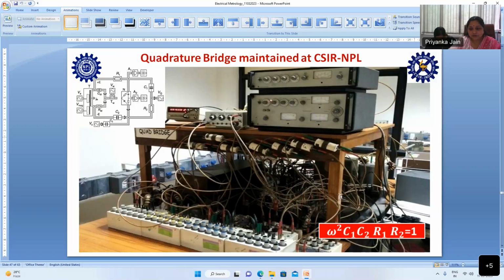The balance condition for this quadrature bridge is omega squared C1 C2 R1 R2 equal to 1, where omega is the angular frequency, with a frequency of 1592 Hz providing omega equal to 10 to the power 4. So if you go through this equation, with omega at 10 to the power 4, C1 C2 will be on the order of 1 nanofarad and R1 R2 on the order of 100 kilo ohm. This is how we have designed our quadrature bridge. This is maintained and operational at NPL India for the dissemination of traceability of resistance standards.